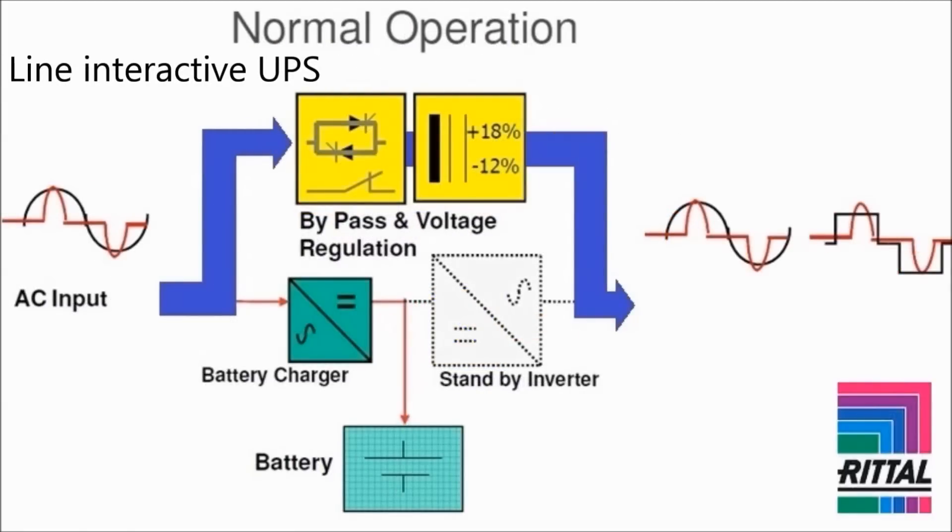Similar to the standby or offline UPS, during normal operation, the line interactive UPS passes the AC input through a bypass switch to the output. But the line interactive UPS also includes a voltage regulator capable of smoothing out spikes in the supplied AC power before feeding through to the output. However, like the bypass UPS, the line interactive UPS does not protect equipment during the change over time between failure of mains power and inverter startup.